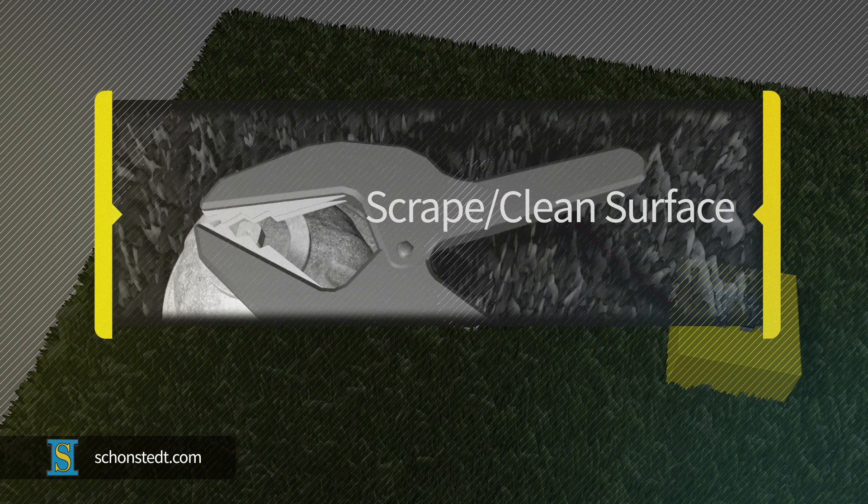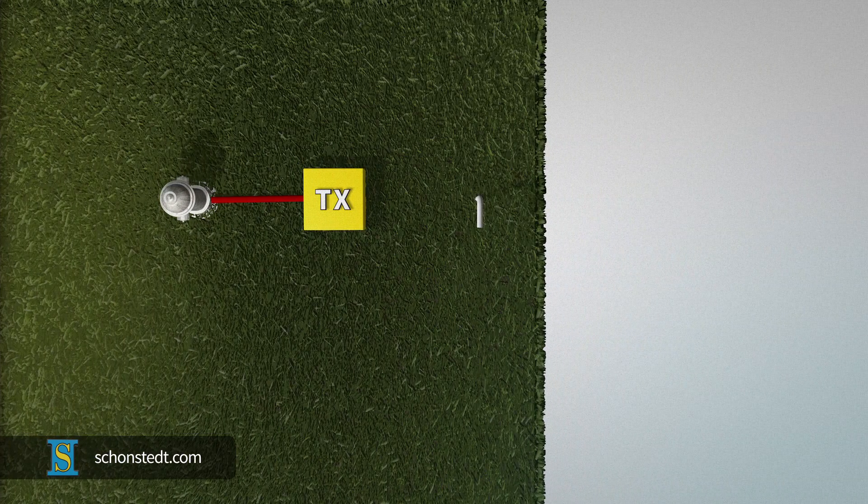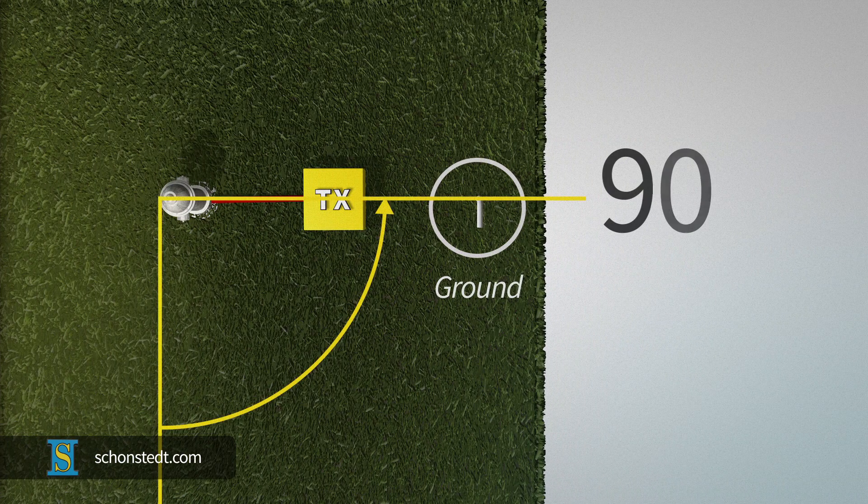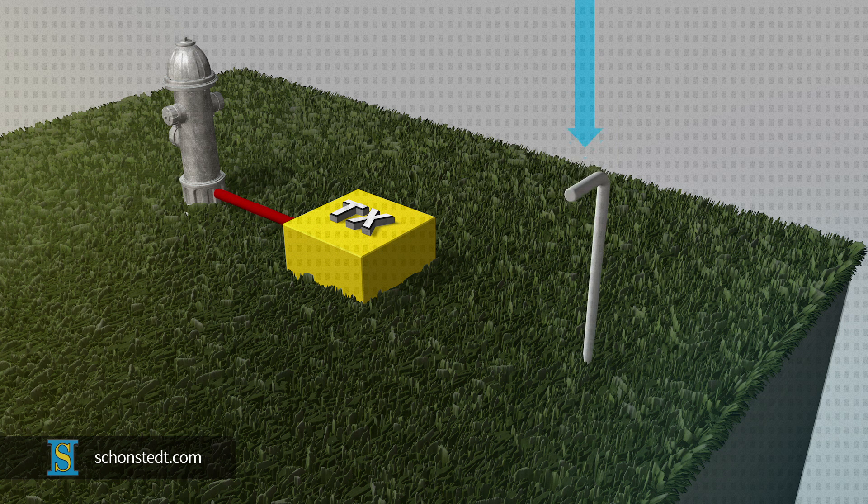For best results, you may need to scrape or clean the surface at the point of contact. Next, position a ground stake as close to 90 degrees as possible to the anticipated line location path. Press the stake deep into the ground to increase surface contact with the soil.